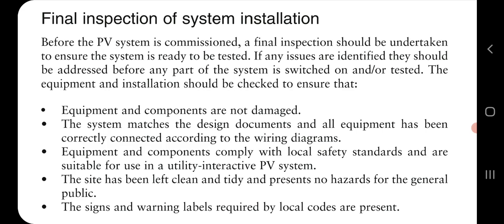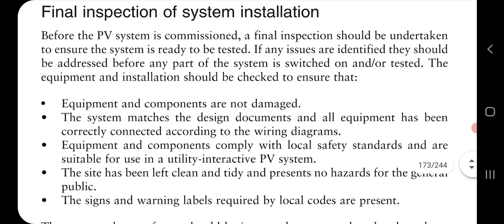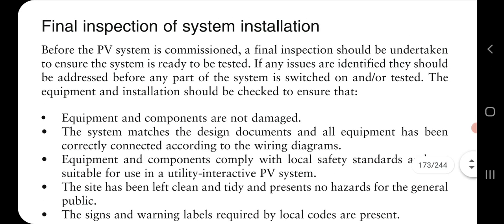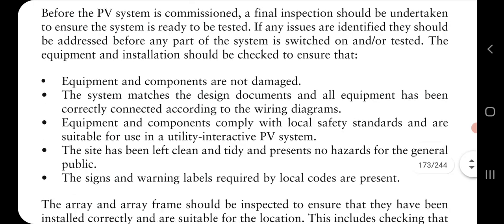You have to see the design document. You have to check that the design document of the equipment is correct, and the wiring also is correct. Equipment and components should comply with the local standards and safety standards, and should be interconnected properly. After completion, the site has to be kept clean and tidy, and there should not be any hazardous material, and the signboard and labels have to be placed as per the local codes.